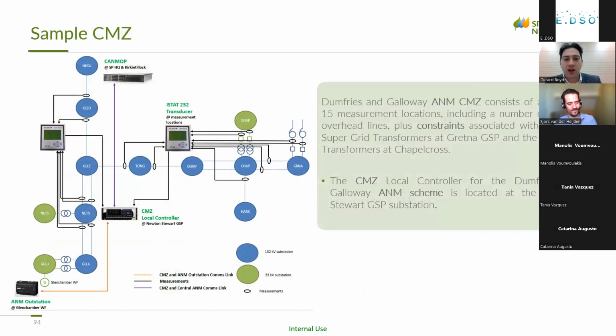So this is an example of one of the CMZs. The blue and green circles are our substations at 132 kV and 33 kV. We've got a number of measurement points, with transducers mostly on the 132 kV network, which in Scotland is actually a transmission voltage, unlike in England and Wales. So you've got transmission measurement points because a number of the constraints are based on the transmission network.